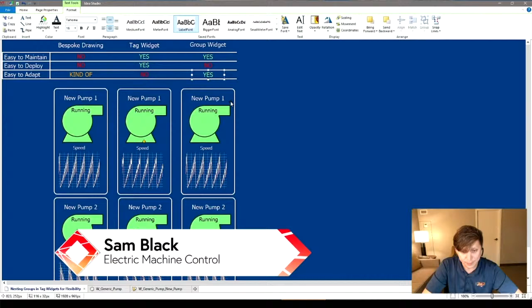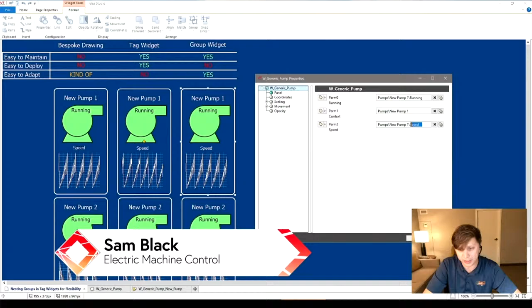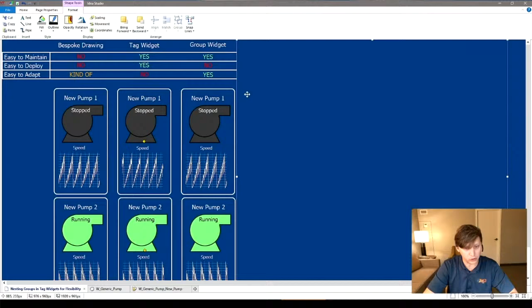So it's easy to maintain—if you make a change here, it's going to go everywhere. It's easy to adapt—you point whatever tag you need at the run signal, whatever tag you need at the speed signal. It's pretty flexible. It's annoying if you're going to be doing 100 of these pumps though. If you've got a new pump you need to make each individual time, you've got to go in, right-click, pick out the running tag, pick out the pump tag, pick out the speed tag. The odds that you're going to forget one of those are pretty high, so you end up having a lot of service calls later in the game as you're trying to fix these things.